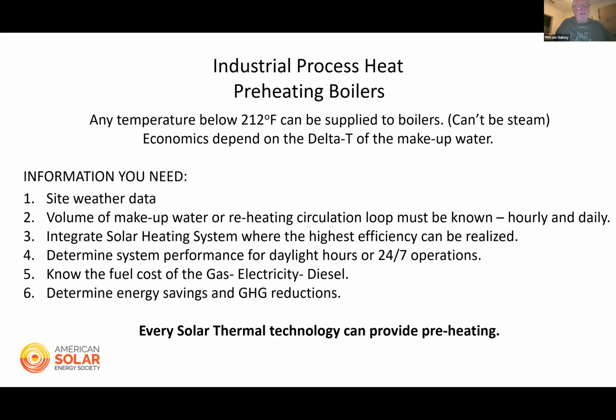So we've got to have site weather data. We've got to have the volume of their makeup water or reheating circulation loop. We need to know that. How many gallons per hour do we have to heat? What is the delta T or the differential for the heating system? Is it groundwater to 200 degrees? Is it a recirculation system that's coming back at 190 degrees, and we need to reheat it to 200 degrees? So we need to know what exactly we're looking to satisfy and how we're going to satisfy it. And we need to know the fuel costs so we can do an economic analysis, whether it be gas, electricity, or diesel, and determining the energy savings and the greenhouse gas reductions will help us sell these systems to the consumer.